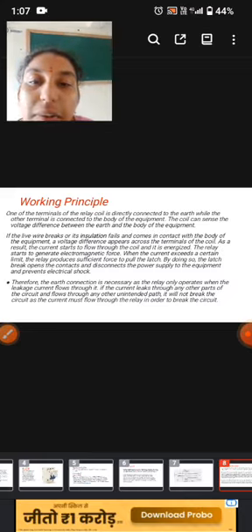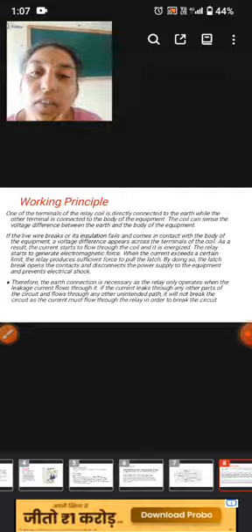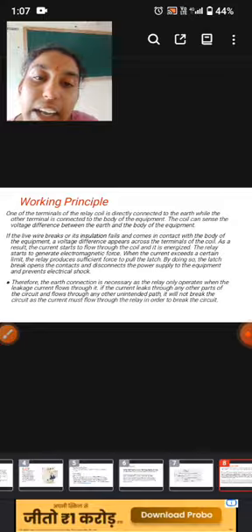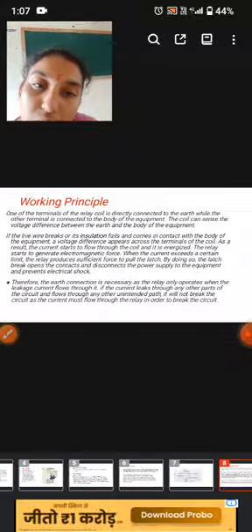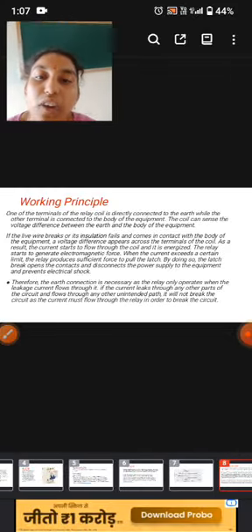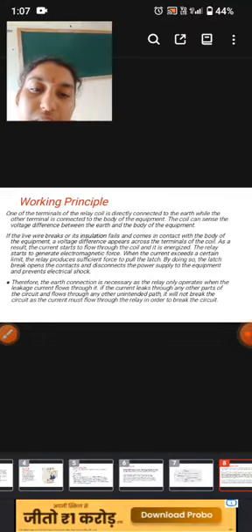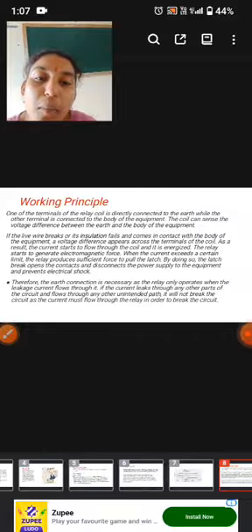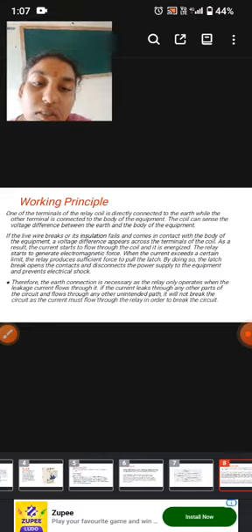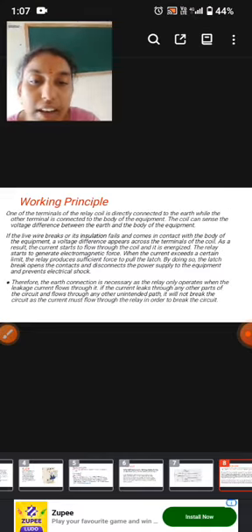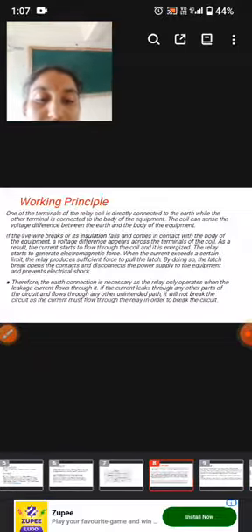Now we will see the working principle of voltage ELCB. One terminal of the relay is directly connected to earth, while the other terminal is connected to the body of the equipment. The coil can sense the voltage difference between the earth and the body of the equipment. Therefore, the earth connection is necessary, as the relay only operates when the leakage current flows through it. If the current leaks through other parts of the circuit and flows through any other unintended path, it will not break the circuit, as the current must flow through the relay in order to break the circuit.